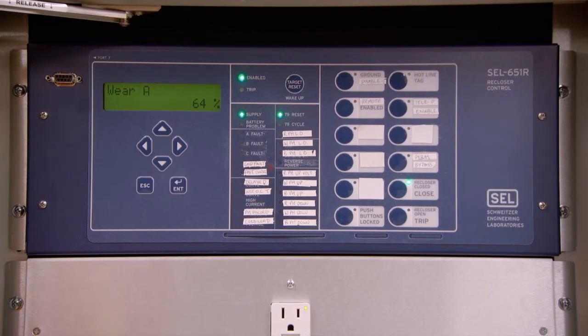The indicator begins with 100%, and as it wears, that percentage goes down. The wear indicator refers to the internal vacuum contacts in the actual recloser. Contact wear is good for 10,000 operations at the minimum threshold of these units. These units are good for 600 amps. So if one were to have 600 amps applied to this and every fault was right at 600 amps, that contact wear life would be 10,000 operations.